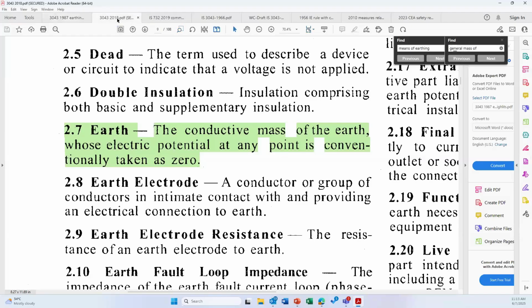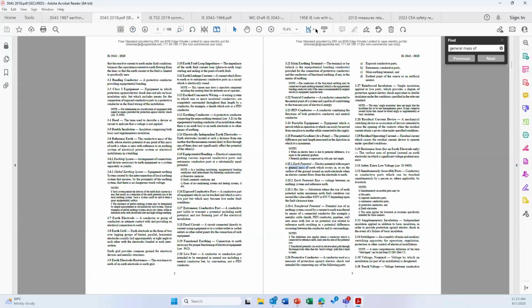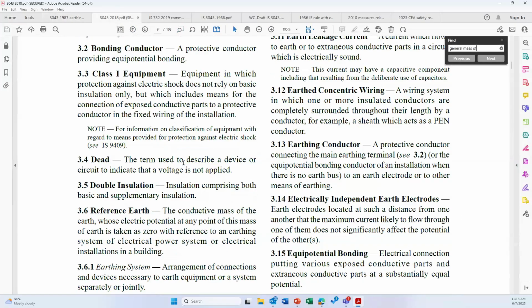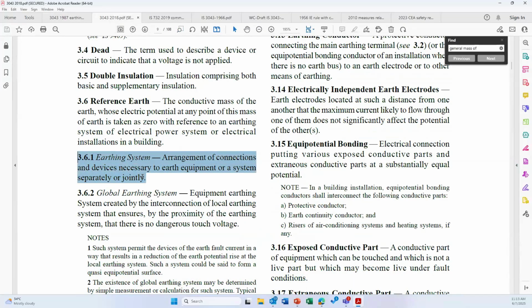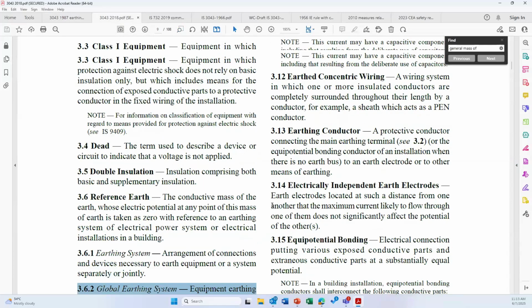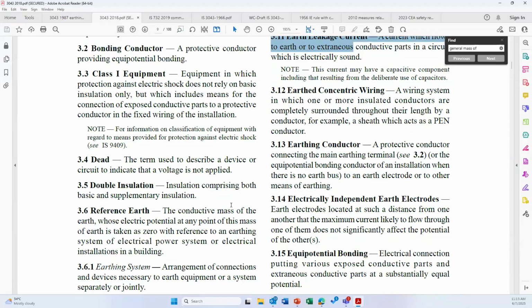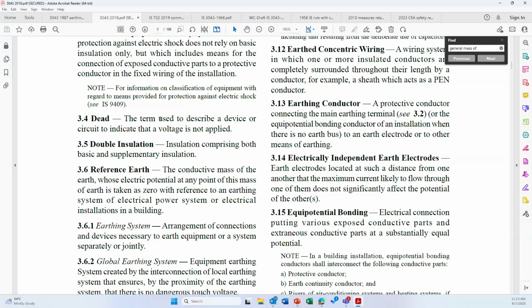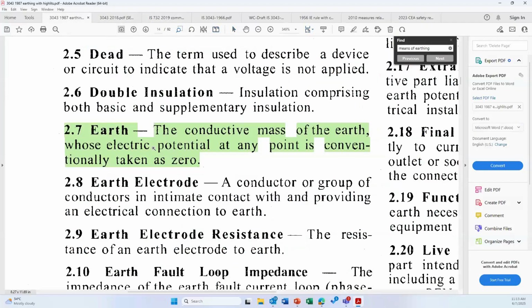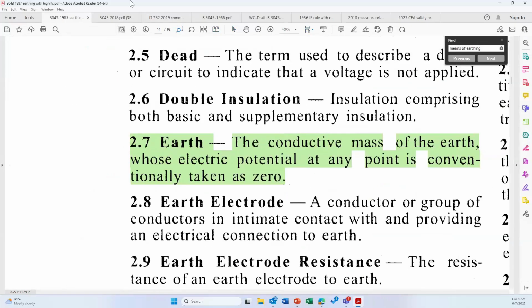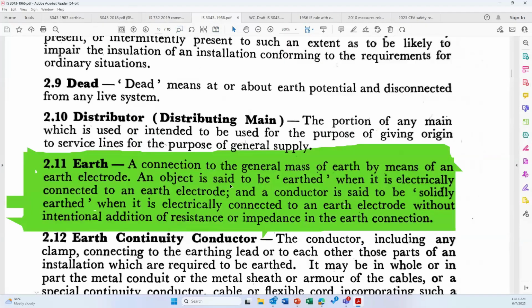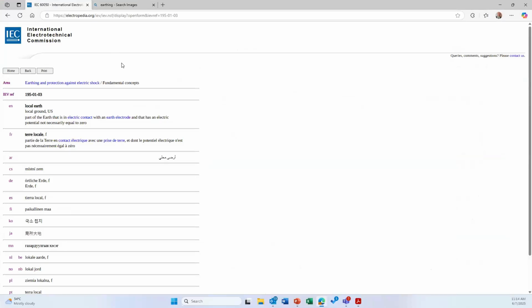In the second edition, 2018 of IS 3043, I don't know how many of you noted, there was no definition for Earth. The definition of Earth itself disappeared. There was only earthing system, global earthing system, and the Earth fault loop impedance. There was a total change. However, because of these old definitions, the idea of connected to earth and so immediate discharge of energy, for example the conductive mass of earth which was there in 1987 or 1966, the general mass of earth by means of an earth electrode, an object is said to be earthed. So these were the definitions which were predominantly used in our country. However, in the modern world, these are not really applicable.